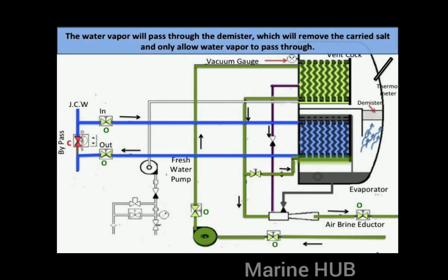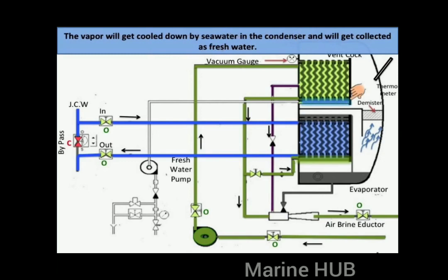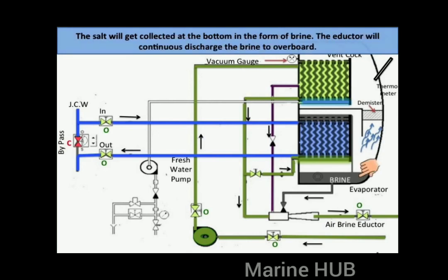The demister removes carried salt and only allows water vapor to pass through. The shell temperature will increase and there will be a slight drop in vacuum — this indicates that evaporation has started. The vapor will then get cooled down by seawater in the condenser and will be collected as fresh water.